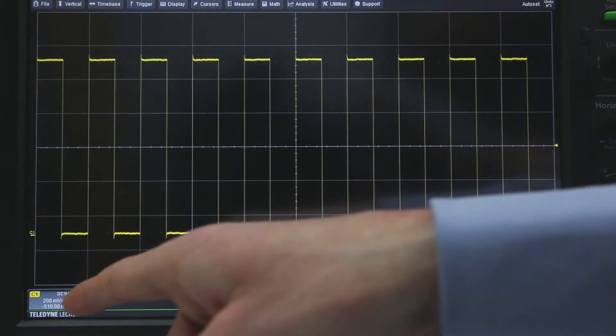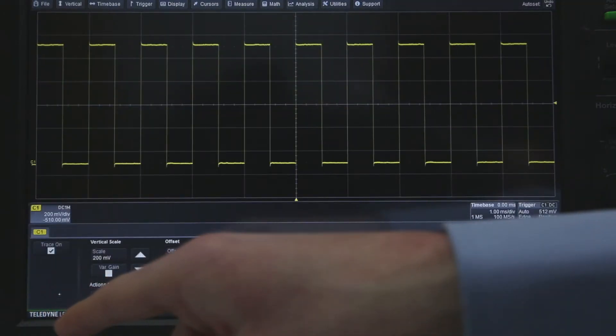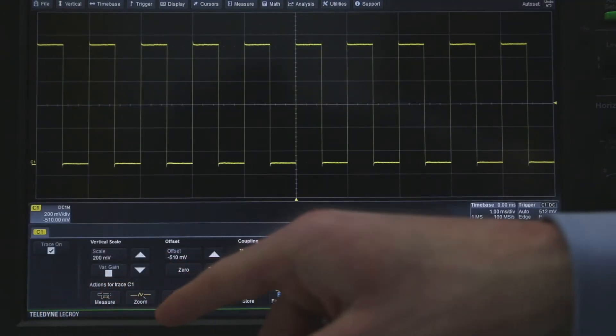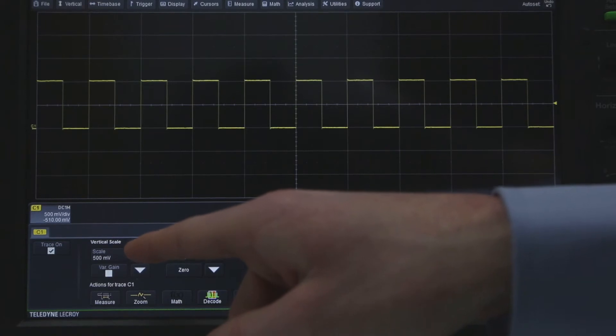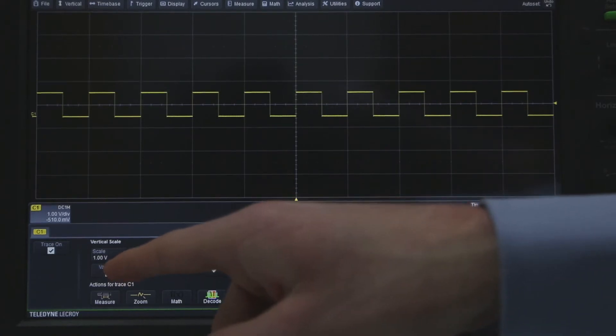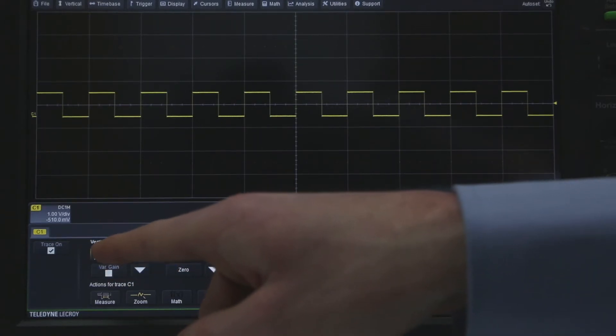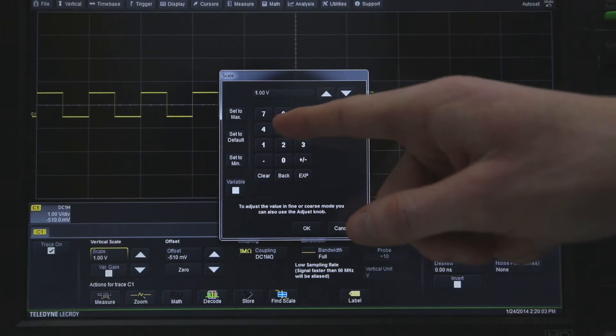Second, is by selecting the dialog box of the channel of interest using the oscilloscope touchscreen, then touching the vertical scale up-down arrow button. Or, by selecting the vertical scale fields and manually entering the value.